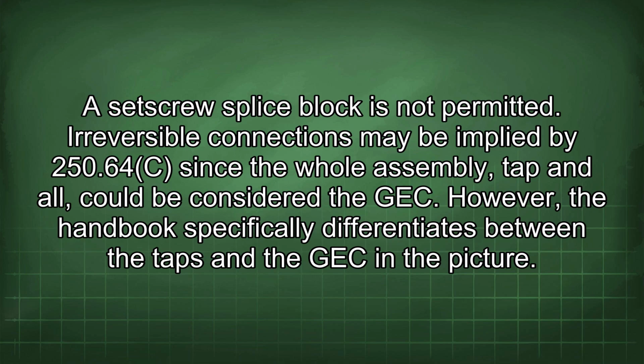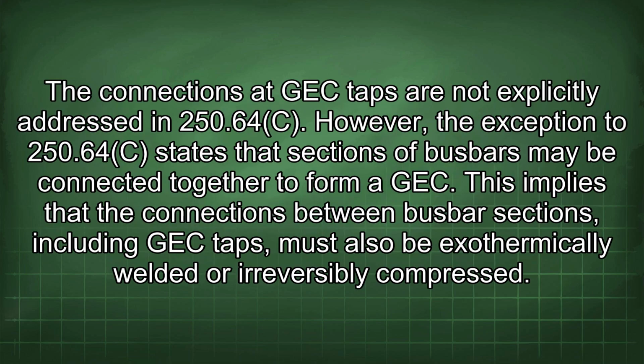Irreversible connections may be implied by 250.64(C) since the whole assembly, tap and all, could be considered the GEC. However, the handbook specifically differentiates between the taps and the GEC in the picture.